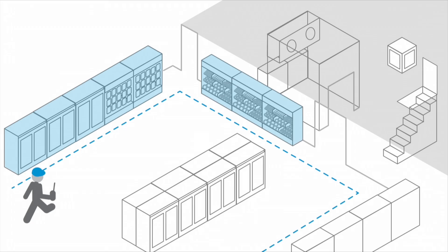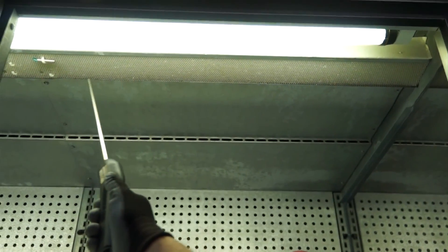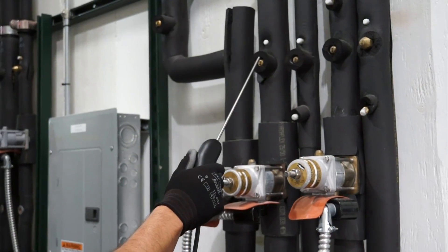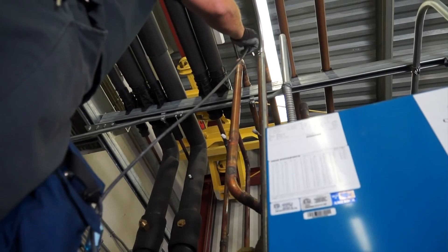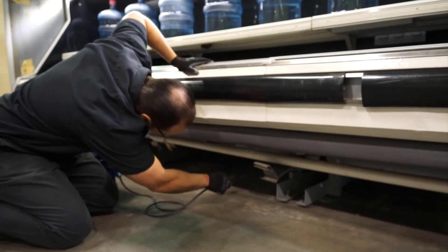Start at one end of the store and check all the cases. Run the leak detector slowly along the honeycomb and check the side of each case where the valves are located. Overhead piping above a T-bar ceiling can be checked at the drops of the display cases and at a midpoint by removing a tile and checking if refrigerant will fall into the T-bar and follow air movement. Exposed overhead piping can be checked by walking the path of the piping with a leak detector. Underground piping needs to be checked at both ends where it penetrates the flooring.